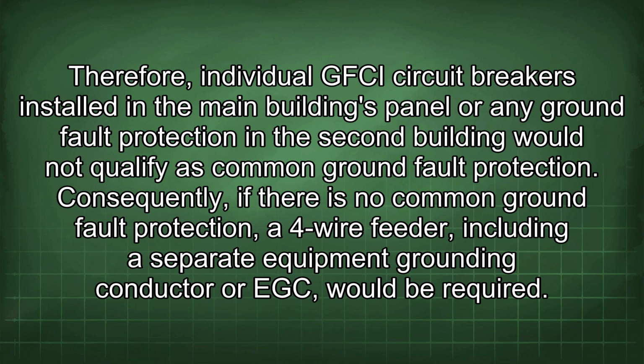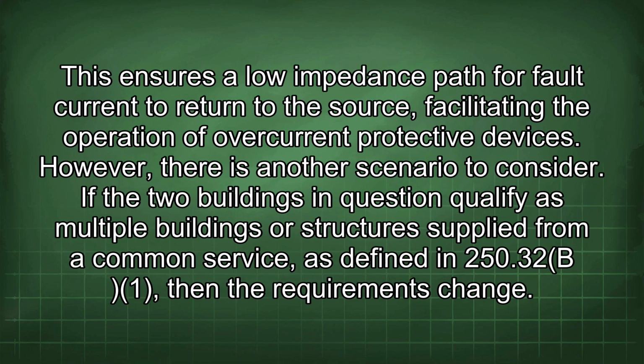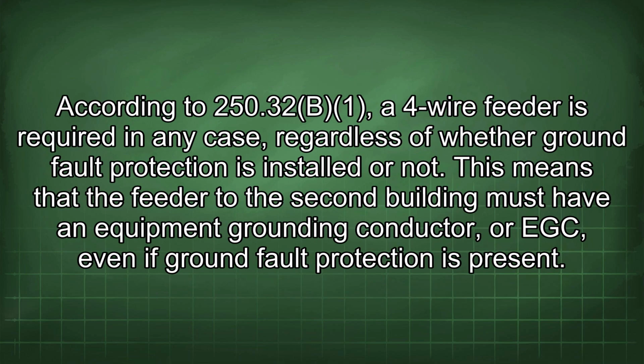Consequently, if there is no common ground fault protection, a 4-wire feeder, including a separate equipment grounding conductor or EGC, would be required. This ensures a low impedance path for fault current to return to the source, facilitating the operation of overcurrent protective devices. However, there is another scenario to consider. If the two buildings in question qualify as multiple buildings or structures supplied from a common service, as defined in 250.32(B)(1), then the requirements change. According to 250.32(B)(1), a 4-wire feeder is required in any case, regardless of whether ground fault protection is installed or not. This means that the feeder to the second building must have an equipment grounding conductor, or EGC, even if ground fault protection is present.